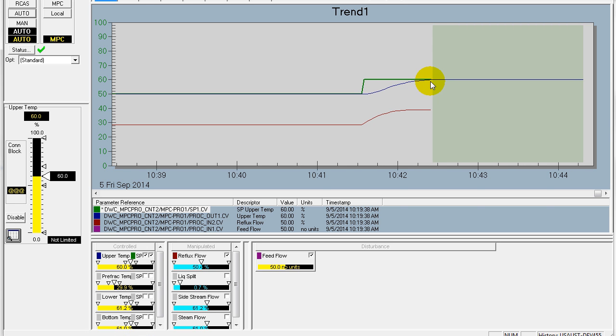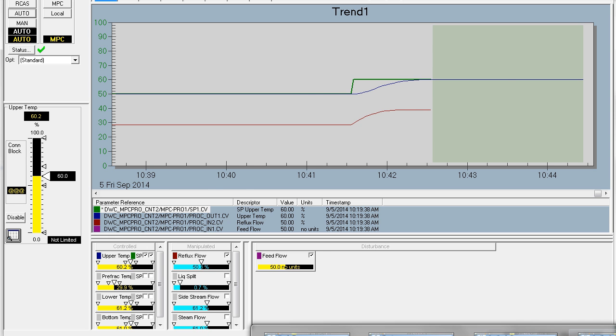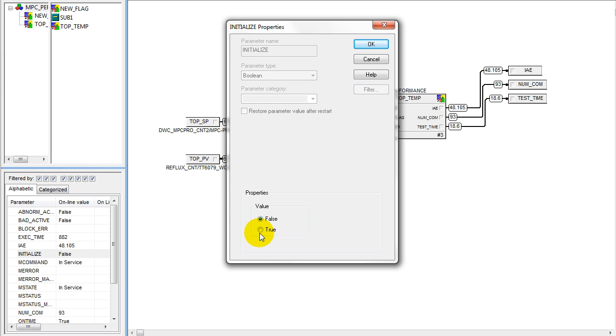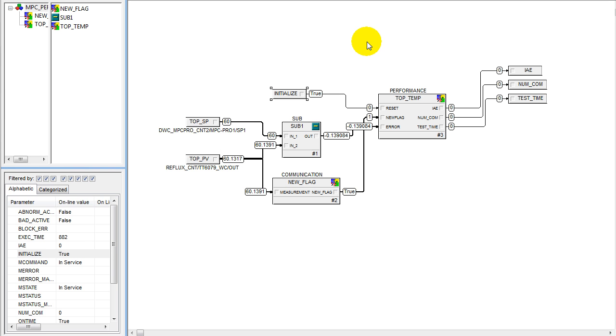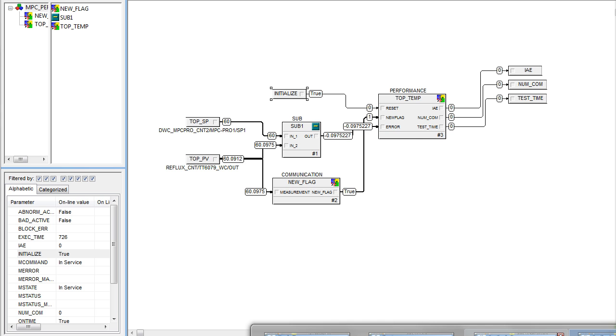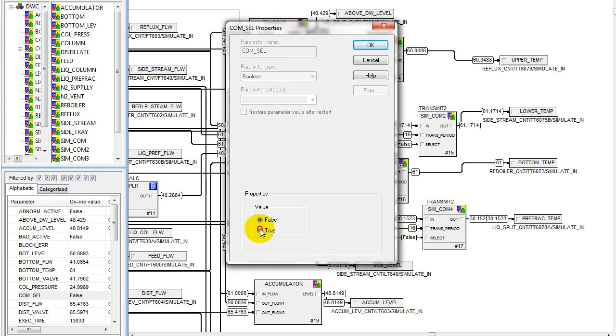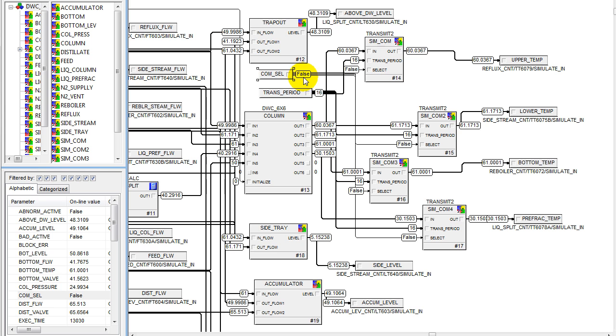Over time, we come up to setpoint. To demonstrate performance using a wireless measurement for the temperature, we'll go back to our performance index. For the wired measurement, we had an integral of absolute error of 47 and 87 communications. We'll zero this out, then go to our simulation and enable wireless measurements. When we enable wireless, the measurement will be simulated as a windowed communication with a deadband of 1%, a period of 16 seconds, and a default of 32 seconds.